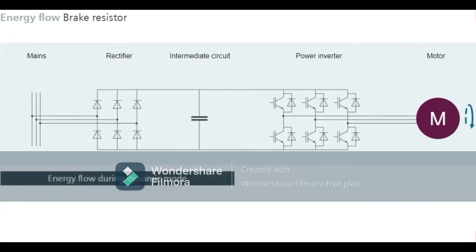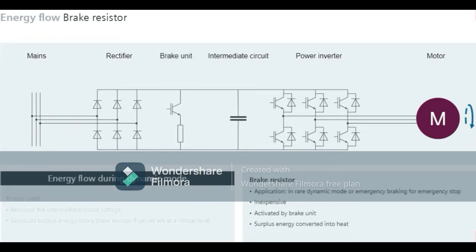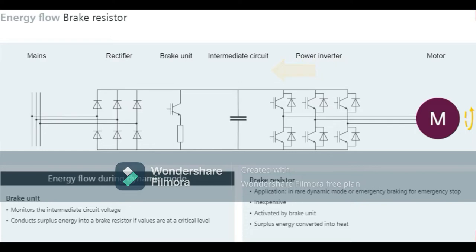If dynamic operation does not occur often, or the drive only needs to be braked suddenly for an emergency stop, using a brake resistor is an inexpensive solution. The brake unit activates a brake resistor which converts surplus energy into heat. The brake unit is essentially a switch which monitors the intermediate circuit voltage. If the voltage increases to a critical level due to dynamic energy flow, the switch closes and channels the surplus energy into a brake resistor.